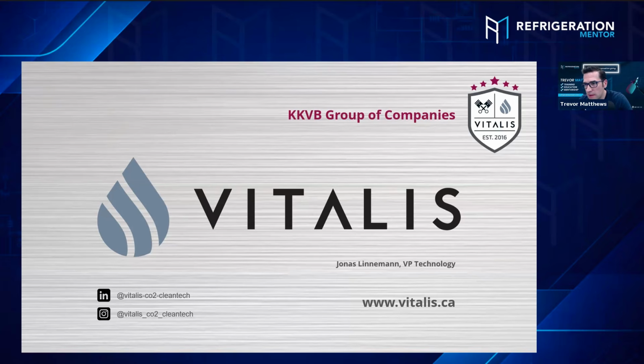I've got a question on scroll compressors. Do you use scroll compressors at all yet? Not really. We do use some, not here in North America. We use some rotary compressors for very small applications like train kitchens or single units for one or two cabinets. But mainly, our systems use semi-hermetic reciprocating compressors. You see that in the large systems, right? You're targeting supermarket and large industrial commercial applications. Yes, because scrolls don't have the capacity. If you need a million BTUs or even 500,000 BTUs, you're going to need a lot more compressors versus a semi-hermetic at this point.